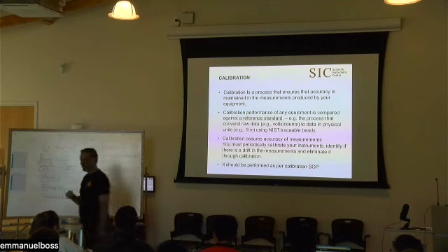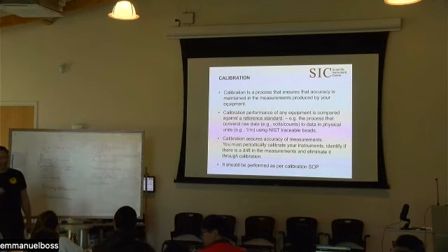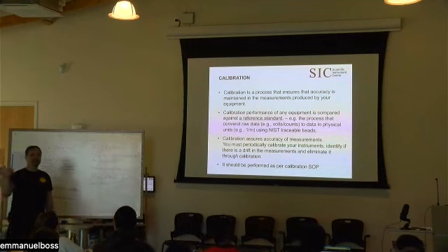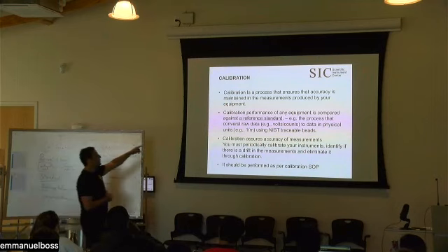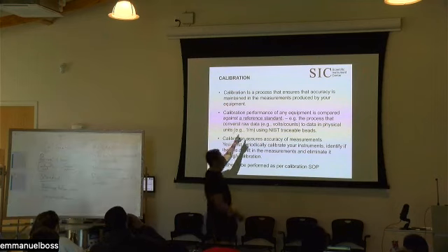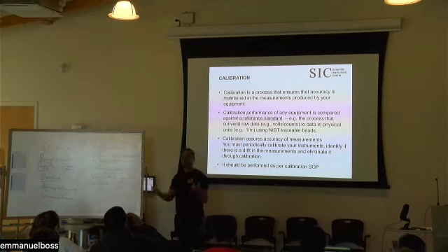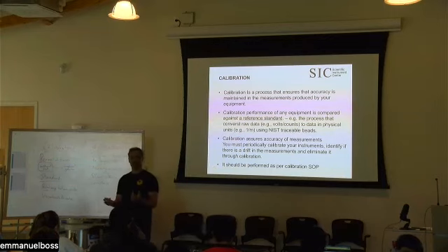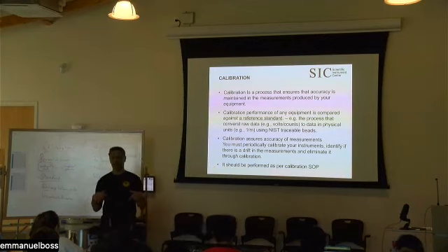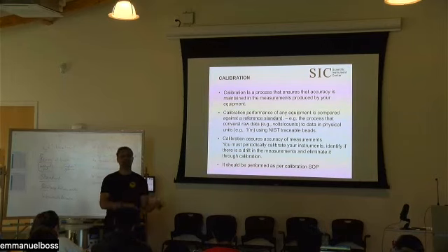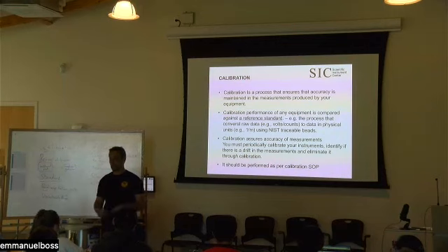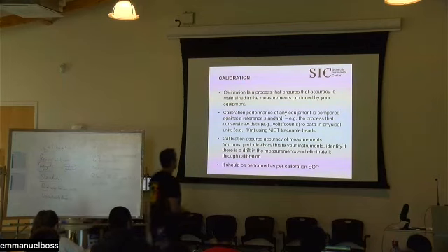I'm very happy to have her here because in my career at least, these are the people we go to make sure that they do several things. One is they help you come up with a calibration procedure for the instrument. And then they test and provide traceable material that you can calibrate with.